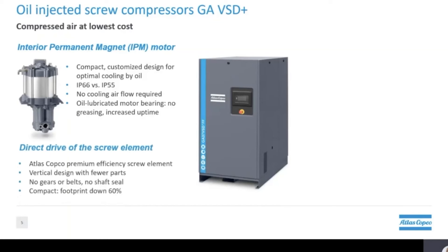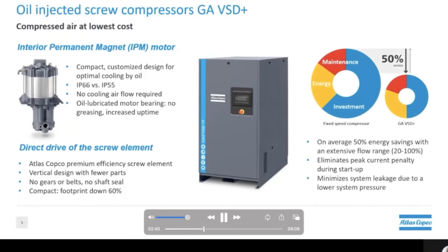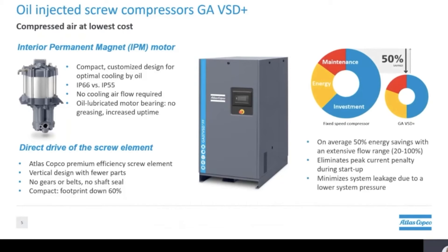Secondly, we have the direct drive screw element. This is another in-house Atlas Copco design which is actually installed vertically. Since the screw is directly coupled with the motor, efficiency is increased. The removal of gears, belts and shaft seals mean that fewer parts are needed, which makes the design more reliable. The vertical design has the additional benefit of reducing the space needed to house the assembly, making our GA VSD+ very compact and reducing the footprint compared to conventional compressors by 60%.